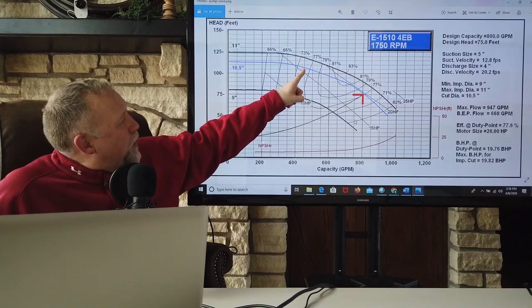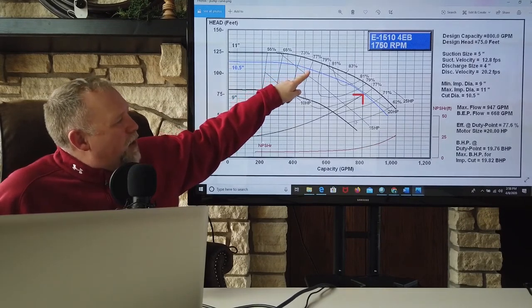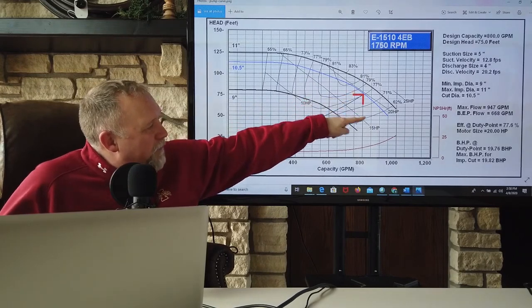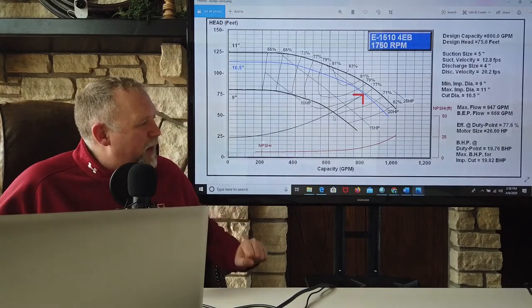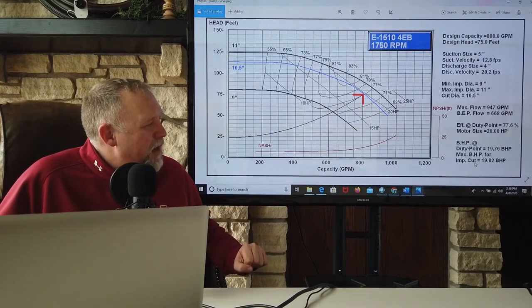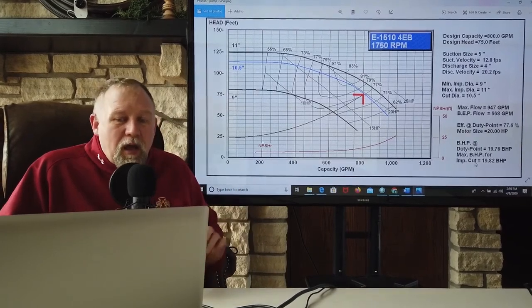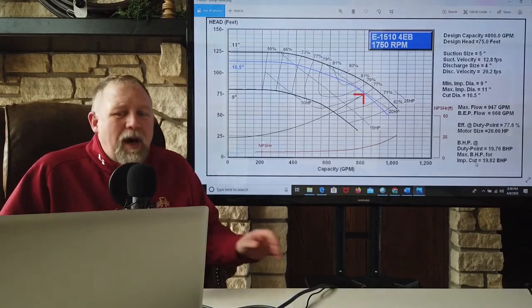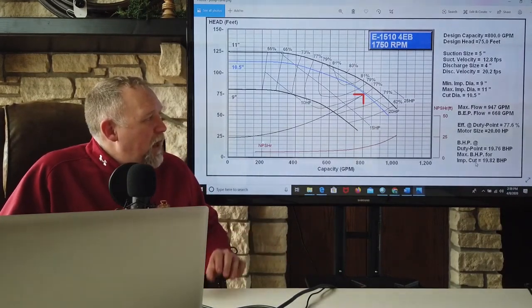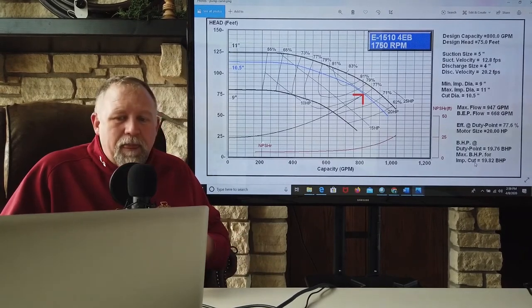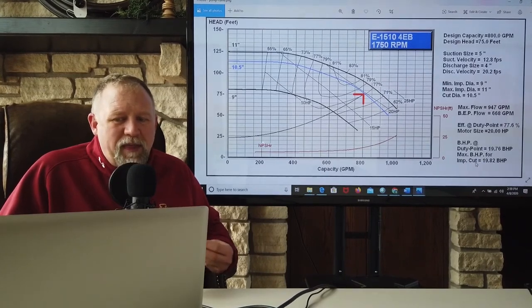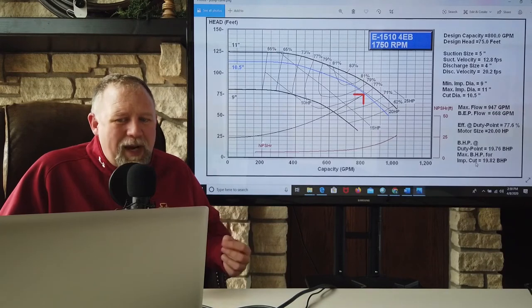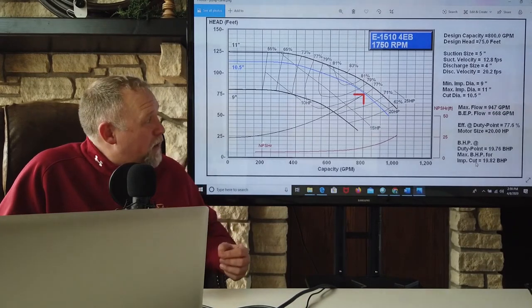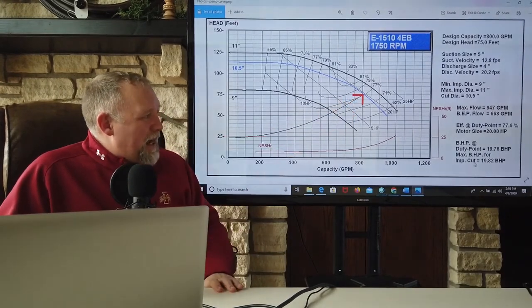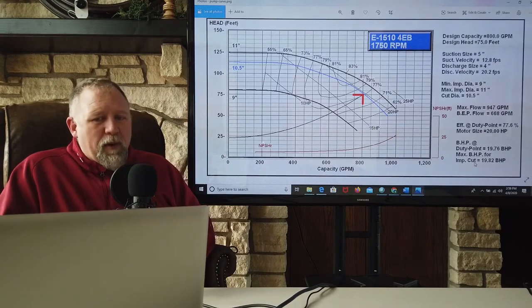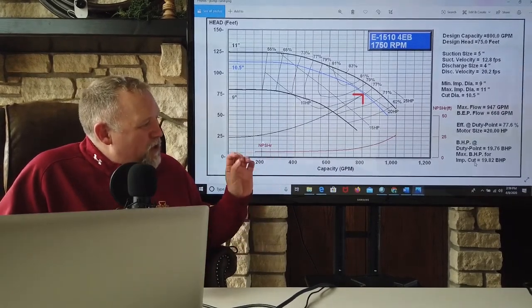If we were operating back here, we'd be operating closer to 15 brake horsepower. Over here, we're operating closer to 20. Notice the maximum brake horsepower for this particular impeller is 19.82 brake horsepower. The question might be, should we go up to a 25 horsepower motor? In my experience as an engineer, I never like to operate within 10% of the rated nameplate horsepower for a motor. In other words, if I expected to operate here day in and day out, I would have picked the 25 horsepower motor even though its operating point was just slightly less.